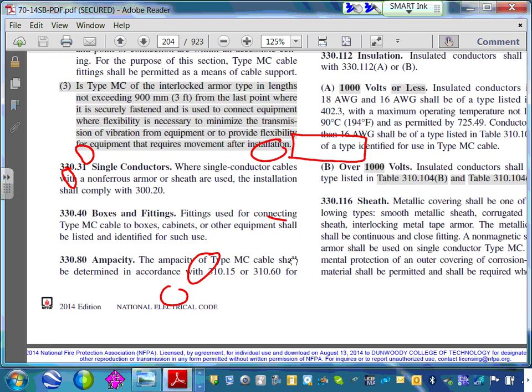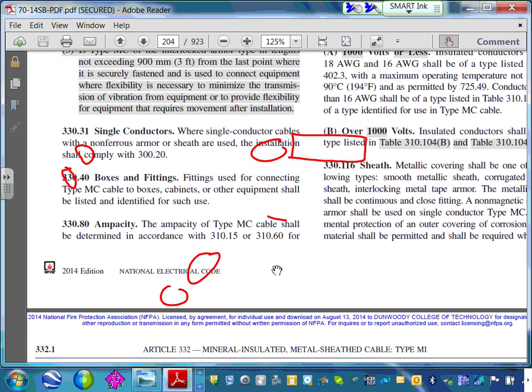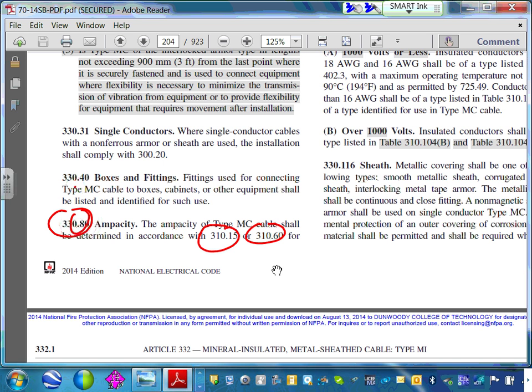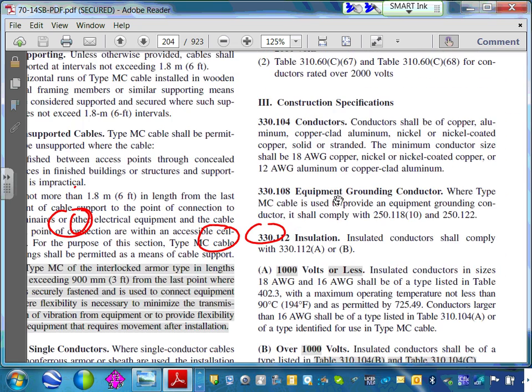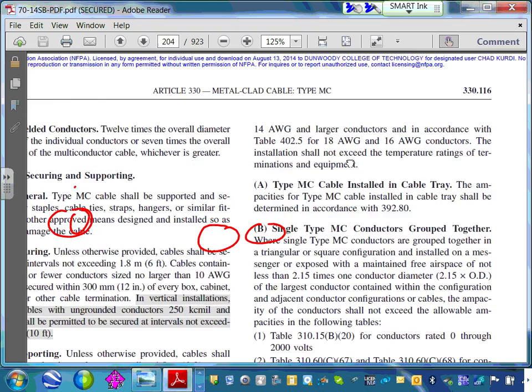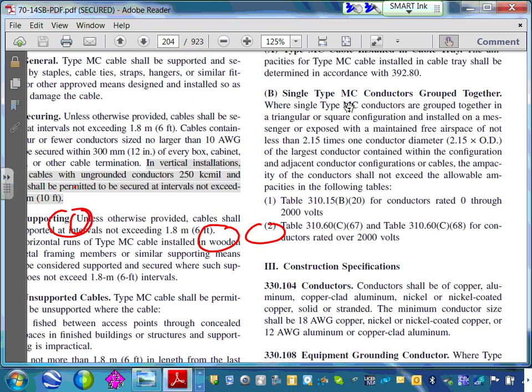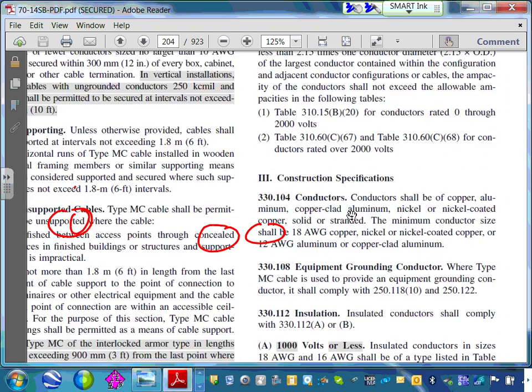Ampacity, this is my favorite. The ampacity of the cable tells you how much current this conductor can carry. Which column do you go to? Every time you see .80, that gives you the ampacity of the cable, referring you to 310.15, and also 310.60 since there's medium voltage involved.